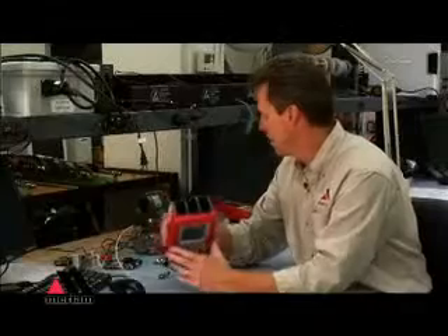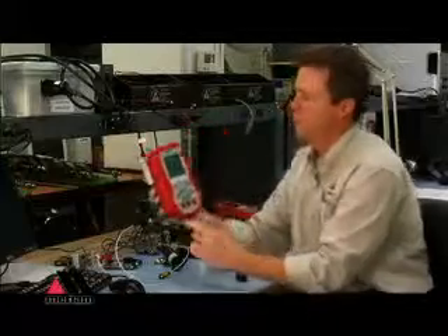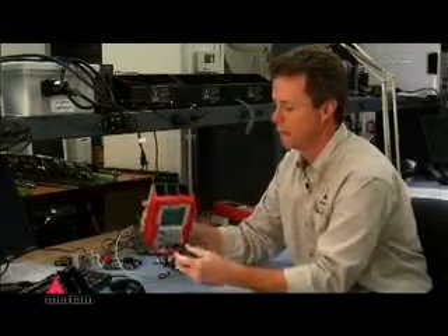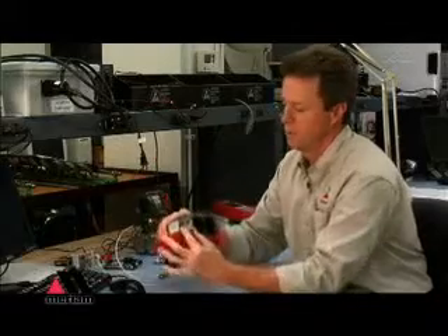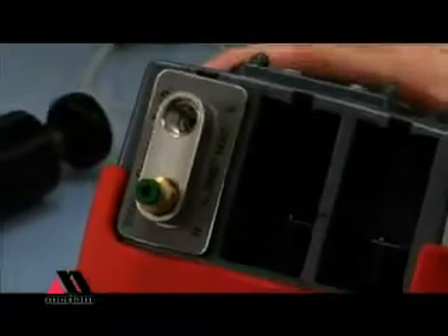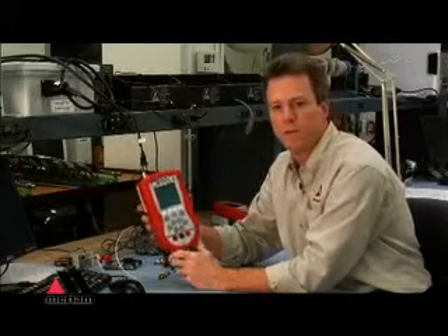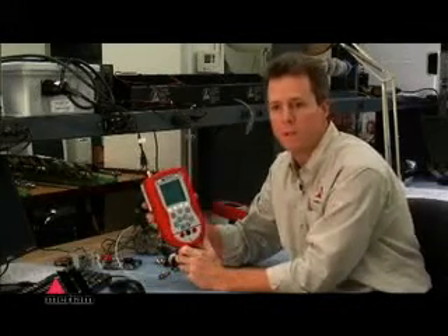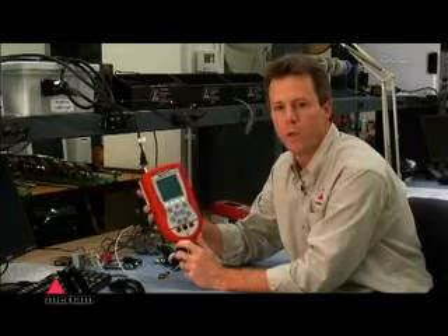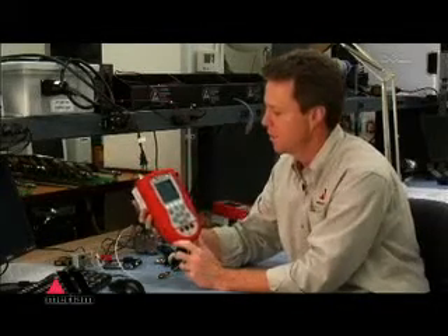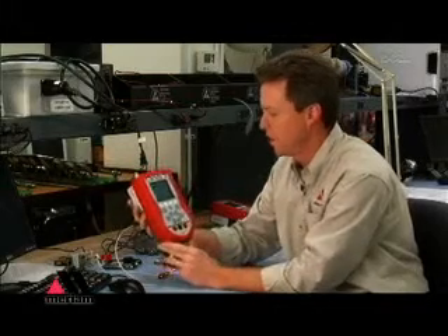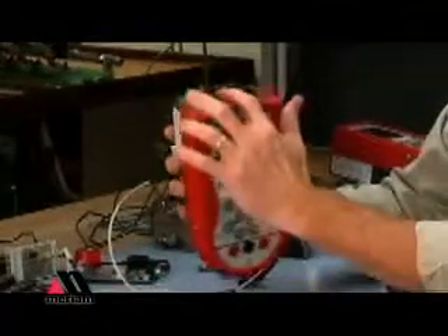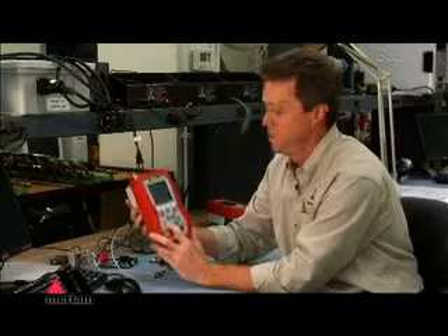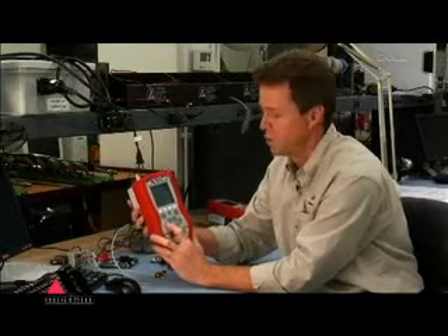The bays in the top will receive any of our modules. We have several types. We do recommend that you turn the unit off before installing a module. So once the base unit is off, insert the module till it clicks and turn the unit on. The module itself carries all the calibration coefficients that's required to make it useful to the base unit. The base unit queries the newly installed module and makes it available for your use and displays it right there for you. If you need to change the unit of measure, press the function key and then the sensor bay location number that you need, and you can adjust any of 11 different pressure units on a pressure module.